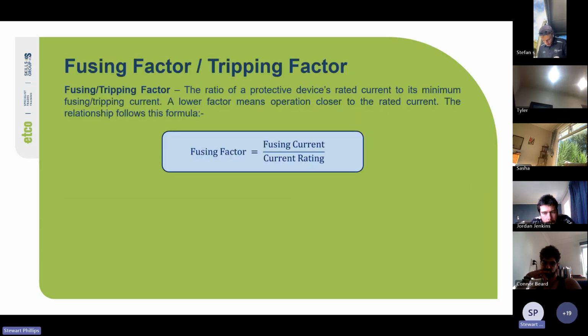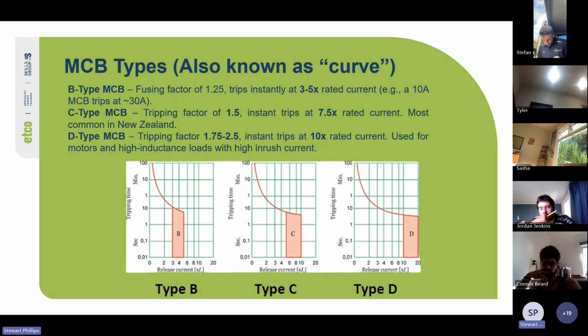So the tripping factor of a type D is 1.75 to 2.5. It instantly trips at 10 times its rated current. The reason it's used for motors and high inductance loads is because when a motor first turns on, it has a high inrush current due to the inductive nature of a motor. There are other ways to start a motor to decrease that inrush current, but you also need to use the correct type of MCB or HRC fuse along with it.